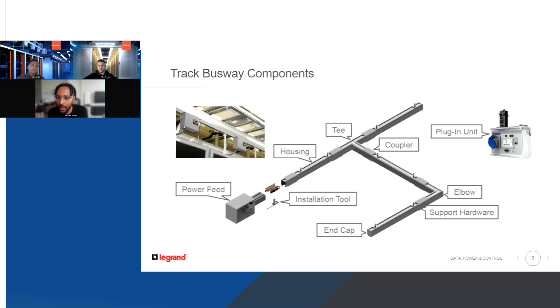Caesar would like to know which points you highlight when you compare copper cables against traditional solutions. I think the question centered around comparing busway to traditional copper or RPP solutions. Really it's the flexibility, it's an open channel bus. The one major point is that with the busway, it's rated or listed to add or remove circuits live. For an RPP or traditional solution, my understanding is that you have to shut down to add or remove a circuit and then route that cable to wherever the load is located. So that's the major point there.